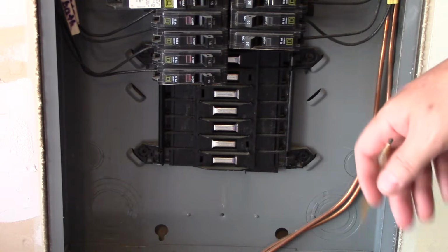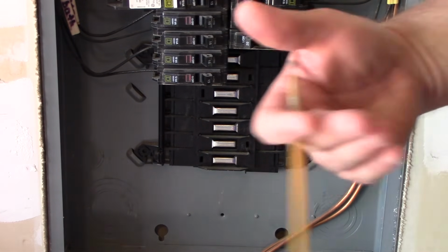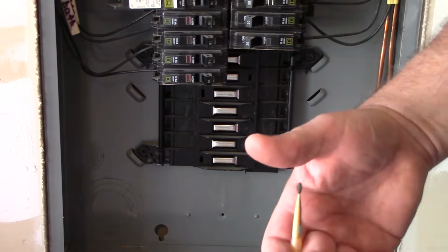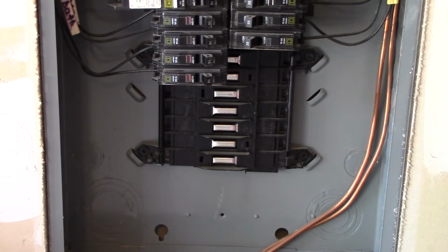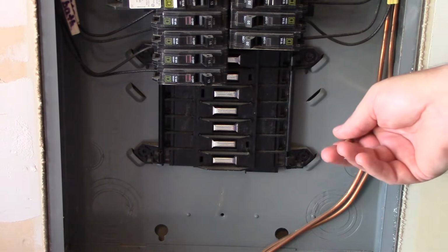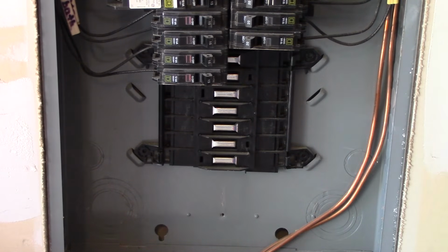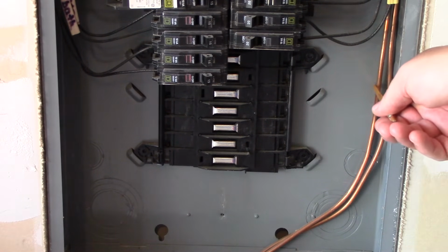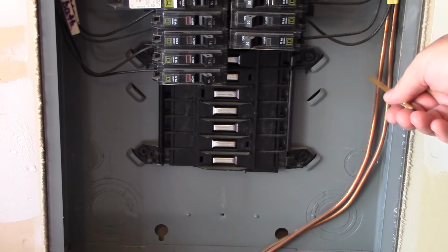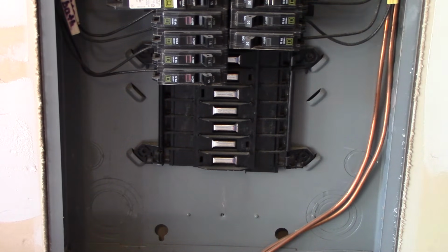Okay, so we have some allowances for those certain types of electrodes, but if it's a water pipe, structural steel, those types of things, then you're actually going to use the table itself, or you can use 250.66 A, B, or C if you have those types of electrodes available. So in this case, it was a concrete encased electrode, so they ran a 4. And they're acceptable for that. Now remember, this grounding electrode conductor has to terminate to the grounded conductor, and it terminates up here on the bus that is in intimate contact with the grounded conductor. Or it could actually have terminated into that lug that's right next to the grounded conductor. That would have been acceptable as well.